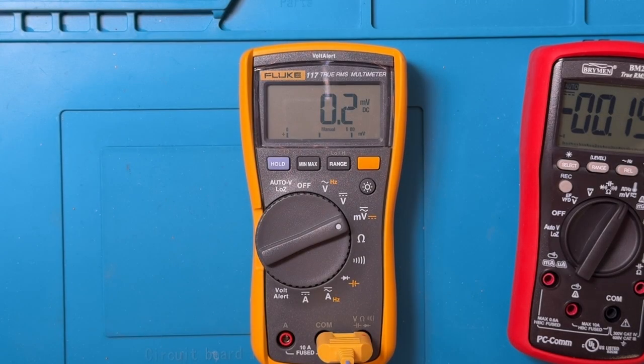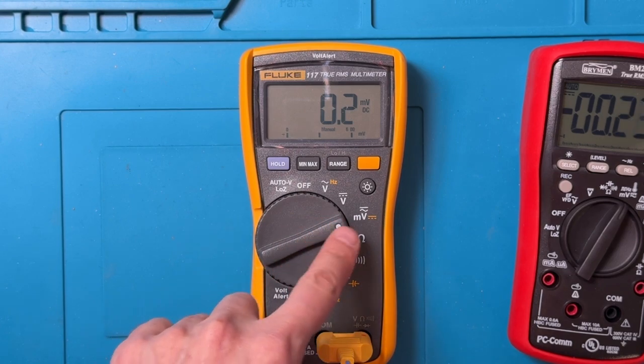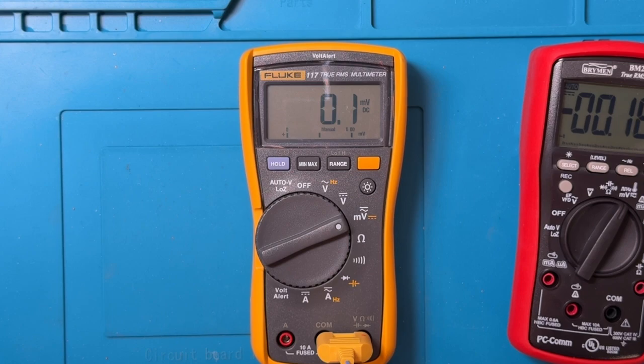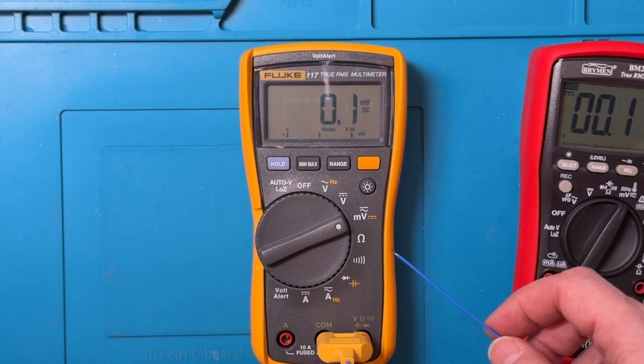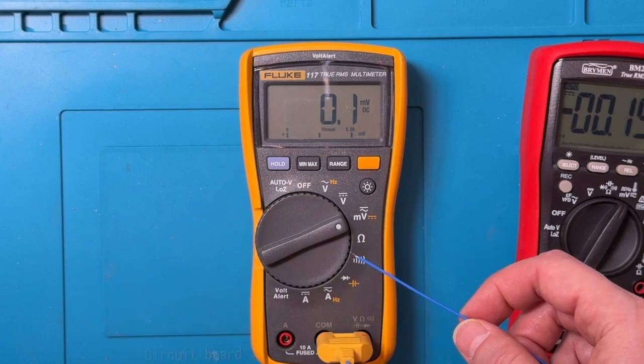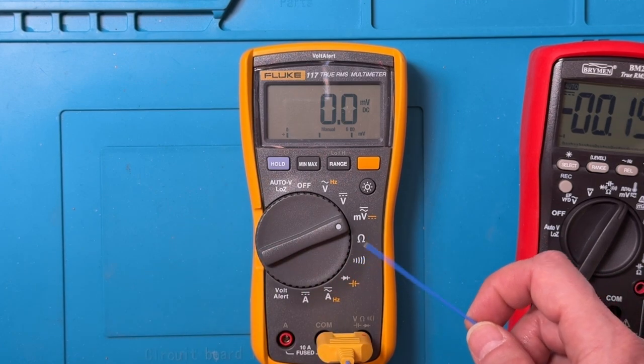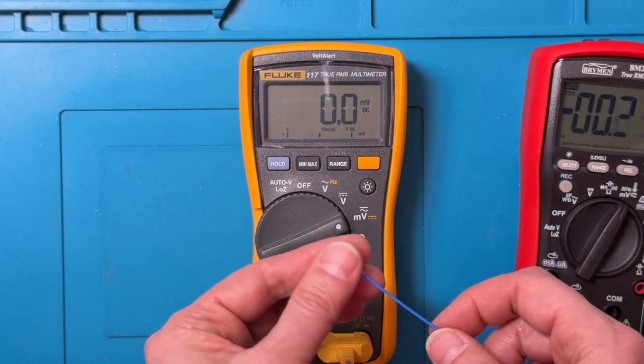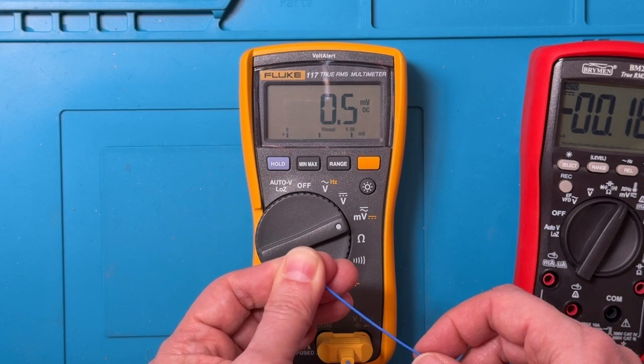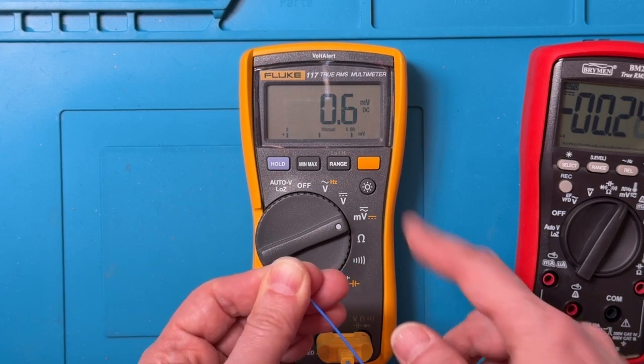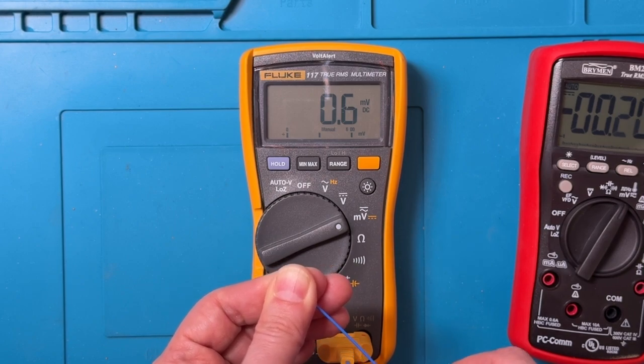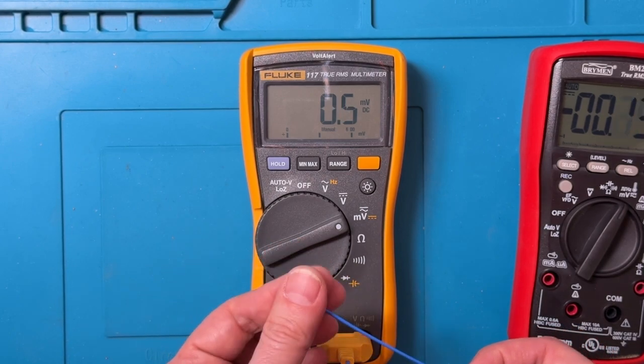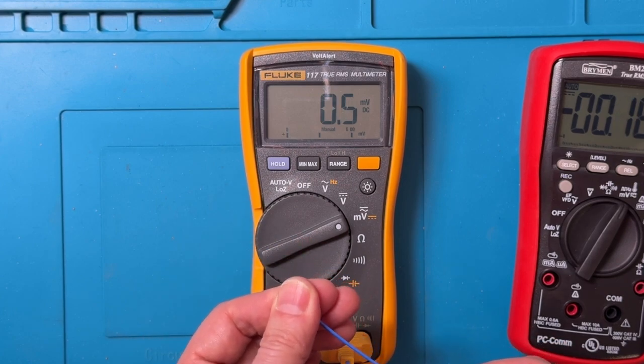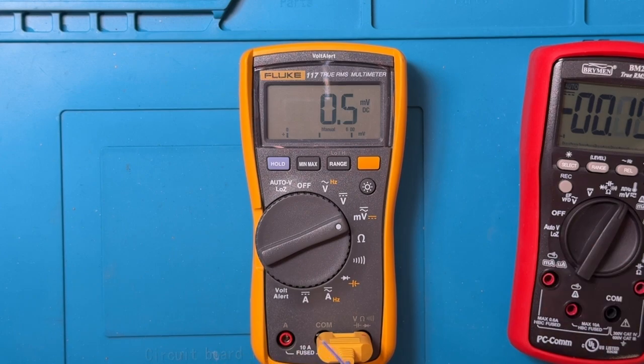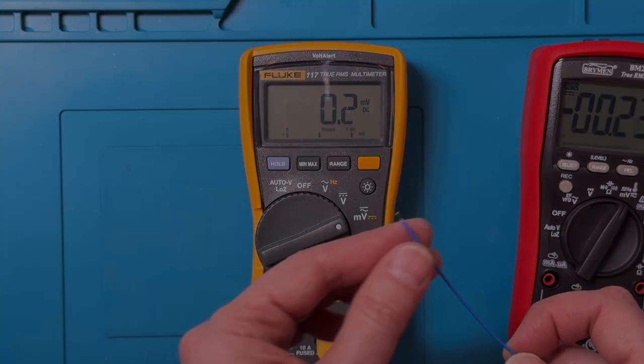Now, just for kicks, I thought, well, the Fluke doesn't have a temperature range, but it does have a millivolt range. And so I said, well, here's the thermocouple. I've plugged it in. And so without me touching it, it's showing 0.1 millivolts. So close to what the Brymen was showing. Now down to 0. If I touch it, this should go up to 0.5, maybe up to 0.6. There we go. So in that sense, there's an interesting correlation in terms of the millivolts. Even though it's not calibrated, we can see that we're getting about the same number of millivolts on the Fluke that we got on the Brymen when we put them into millivolt mode and use the thermocouple here.